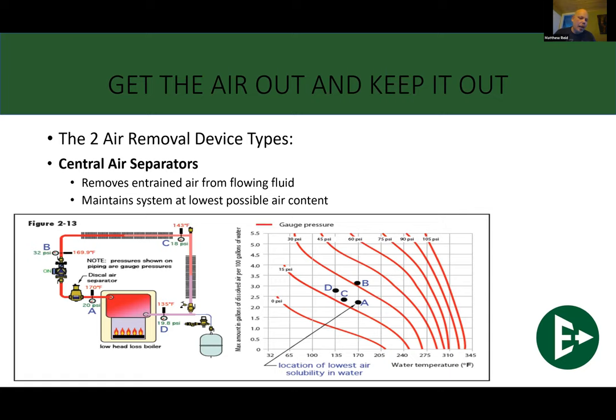Between that and doing a proper system design where you can bleed the air out, usually in the mechanical room, those two pieces combined with a high efficiency air separator, you're going to get the air out absolutely every single time. Couple key rules to follow with high efficiency air separators. Number one, it should be the very first thing that the boiler sees. So you want high temperature and low pressure. That's where your lowest air solubility is in water.